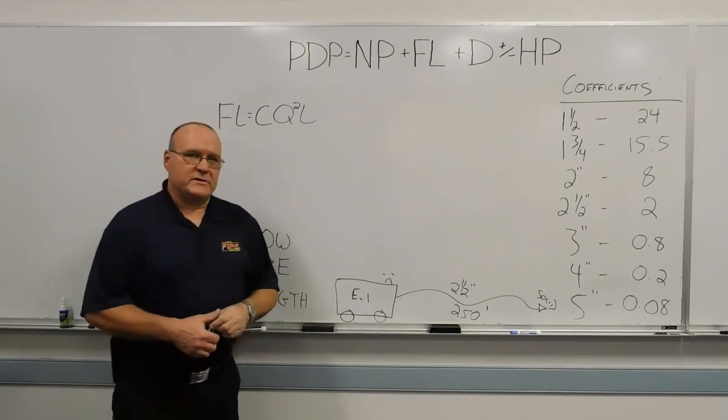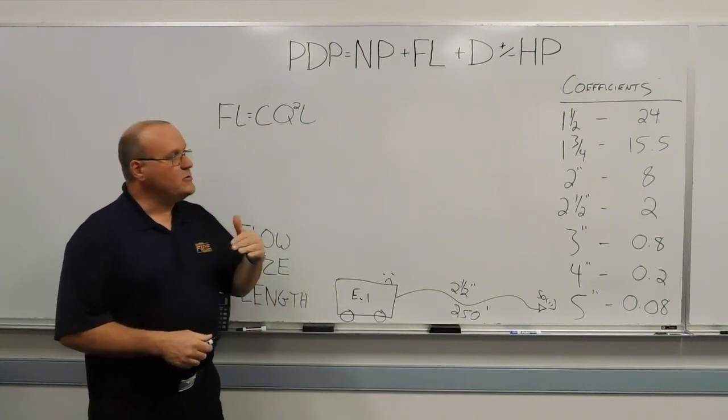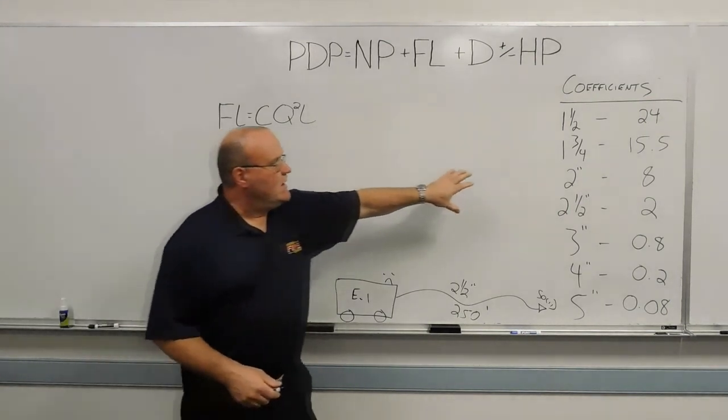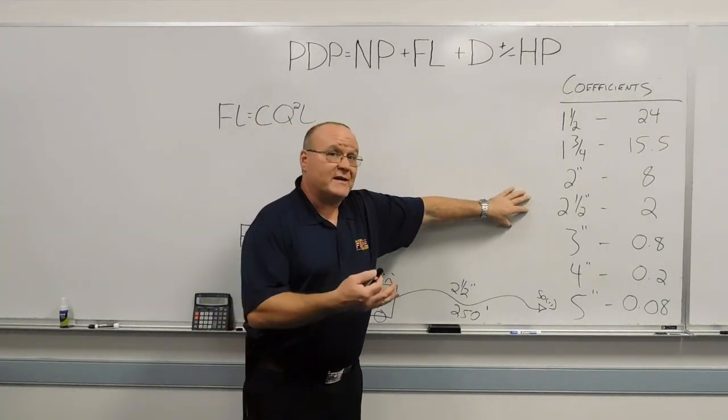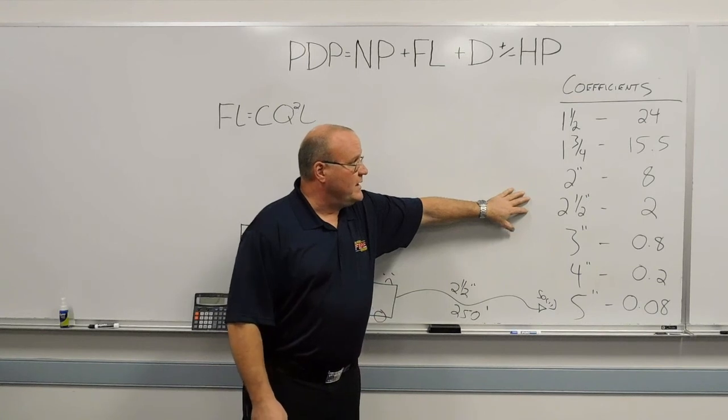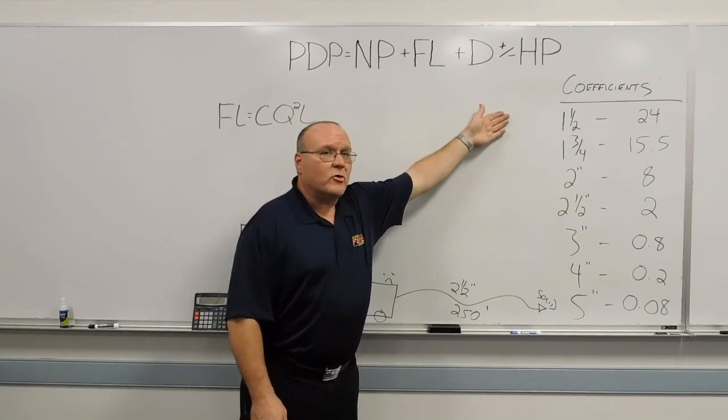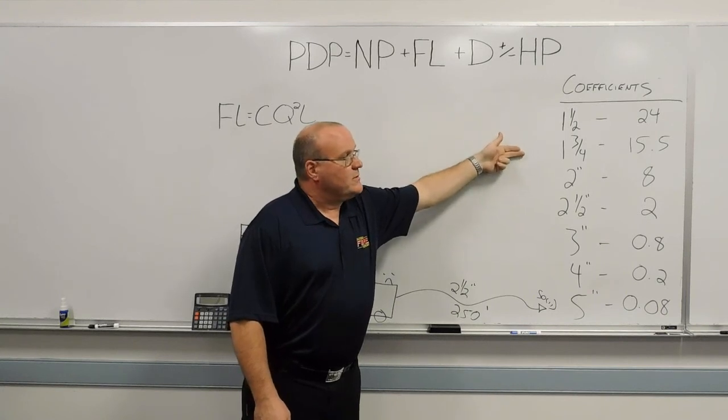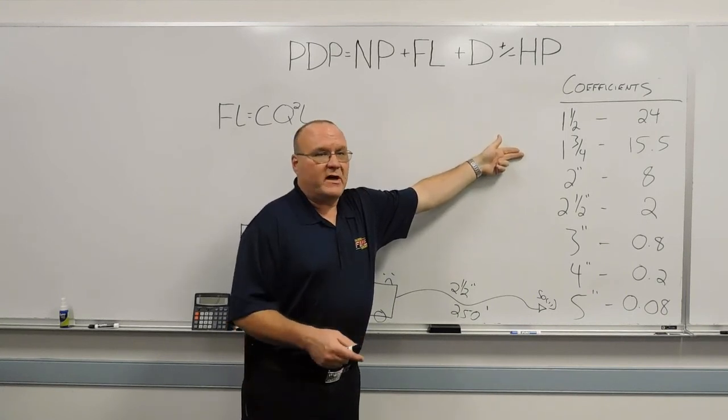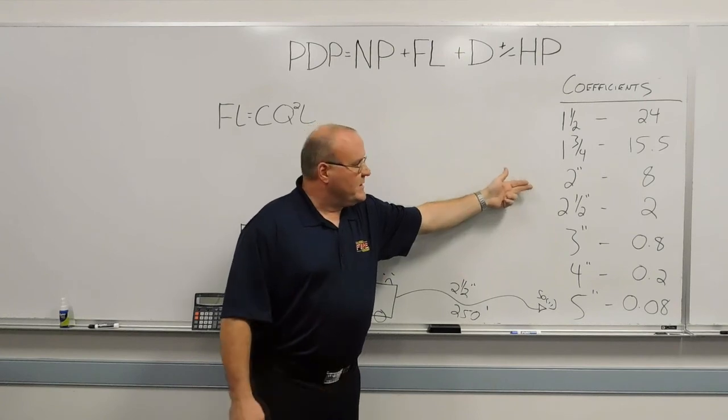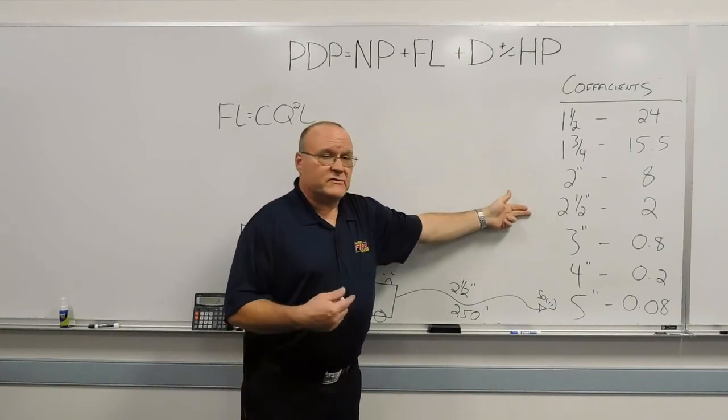As far as the coefficients, if you use some preset numbers, these are some generic coefficients that came out of most texts. The IFSTA text or the NFPA text. Inch-and-a-half hose, the coefficient is 24. Inch-and-three-quarter, the coefficient is 15.5. The two-inch hose is 8. Two-and-a-half-inch hose is 2.